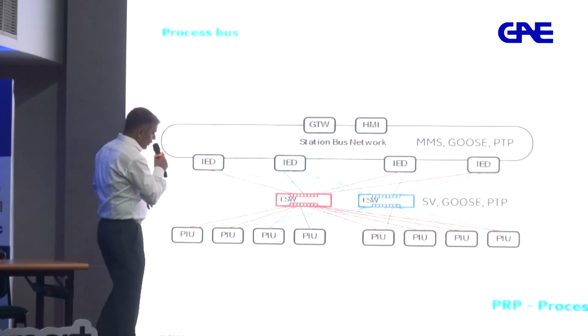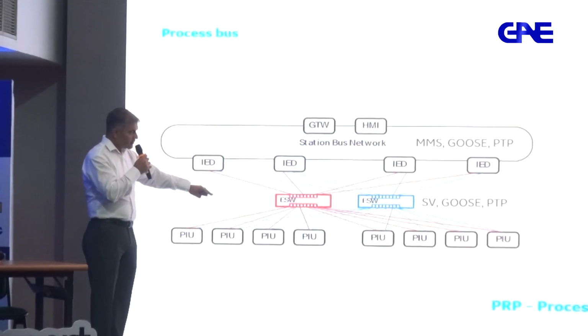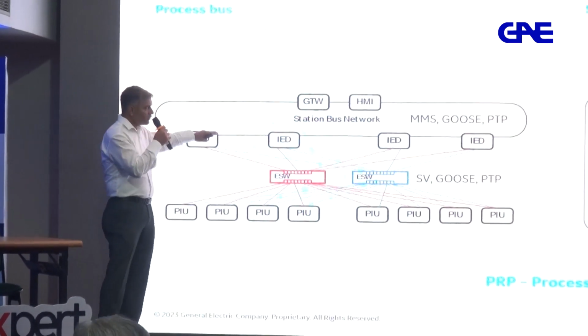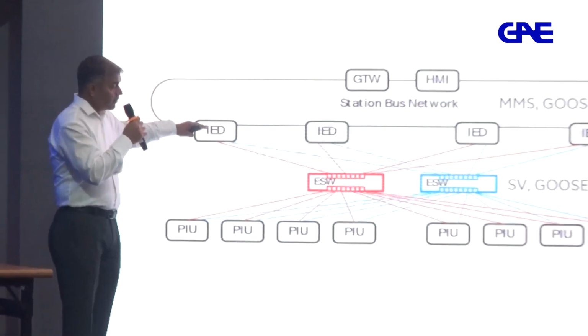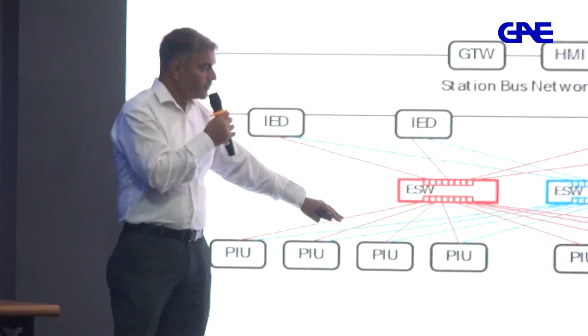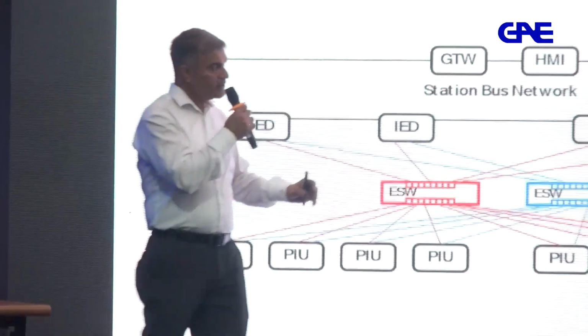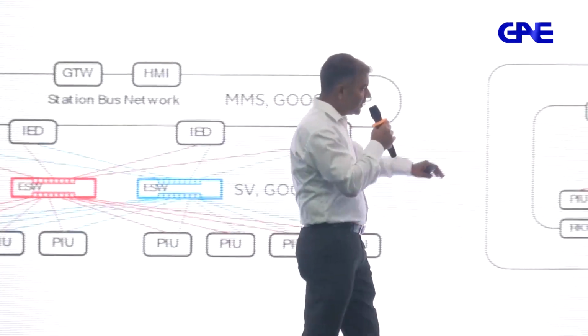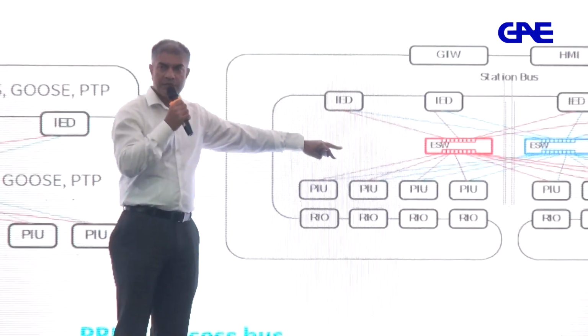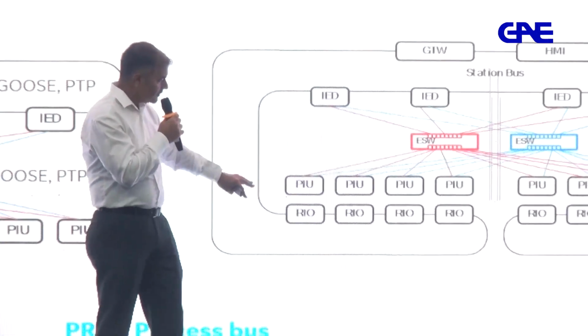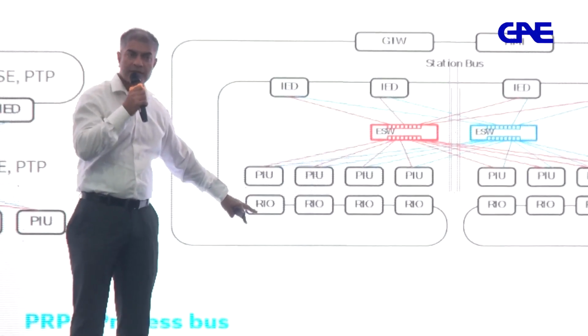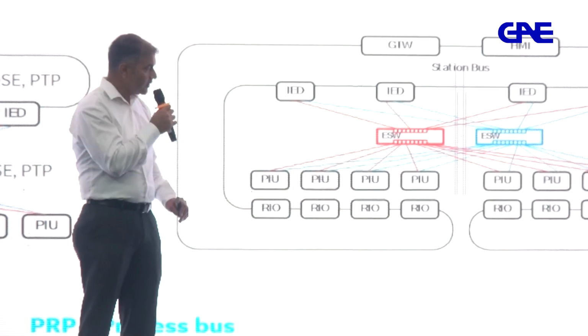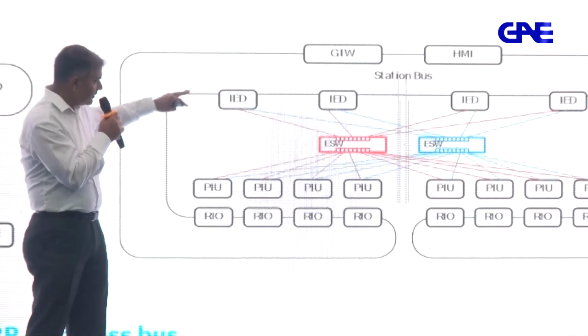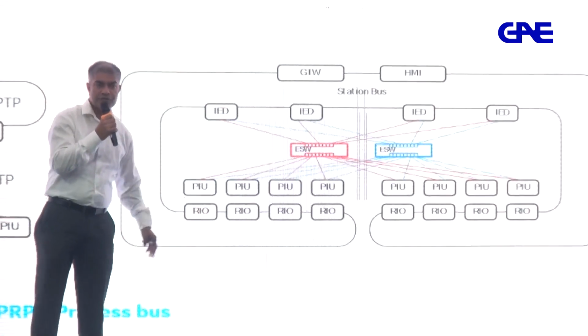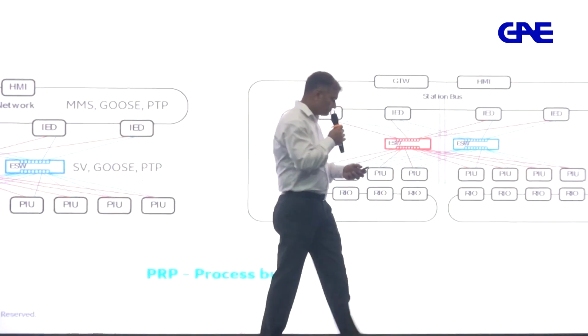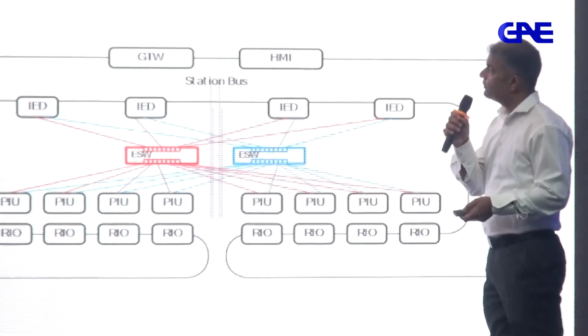Now, you have your process interface unit, merging units, and your IEDs, and this process bus carries all sample values and GOOSE messages. In the other variant, what you have is PIUs - they have only sample values here, and GOOSE messages, trippings, etc. are done by the remote I/O unit. So basically, your station bus is extended to the switchyard - that's one more variant.